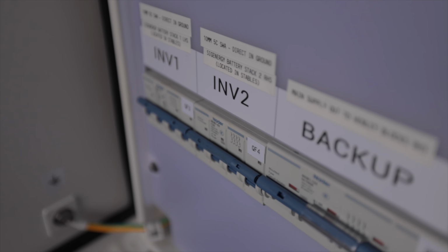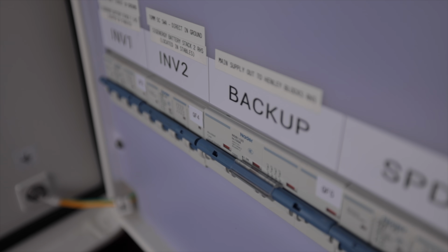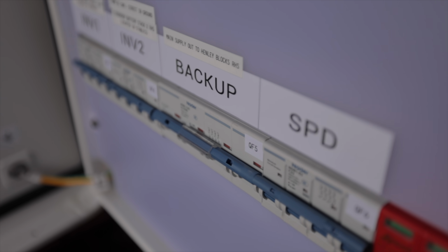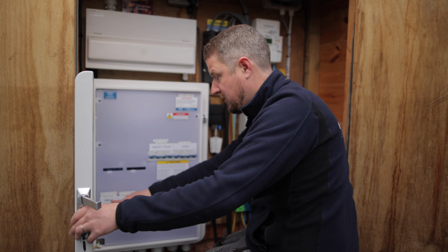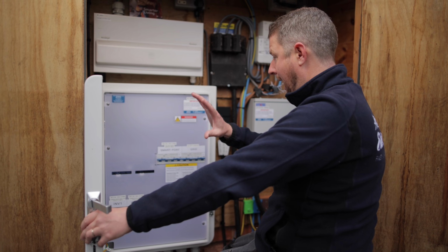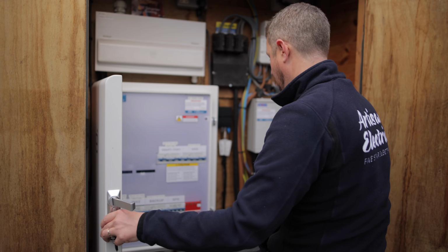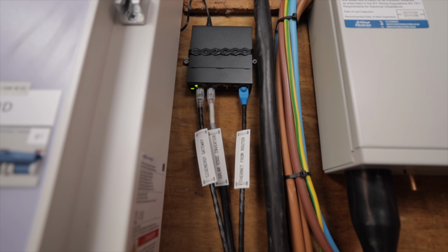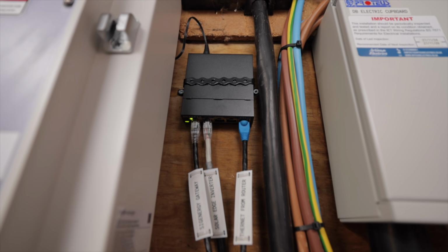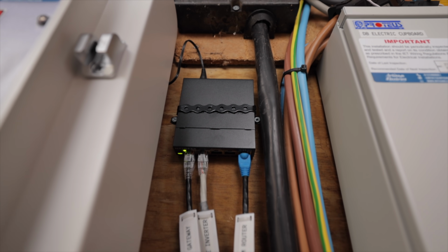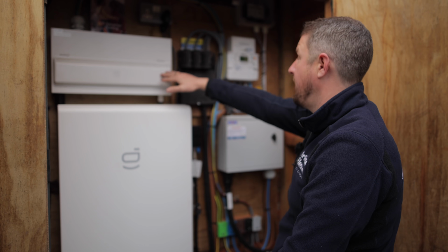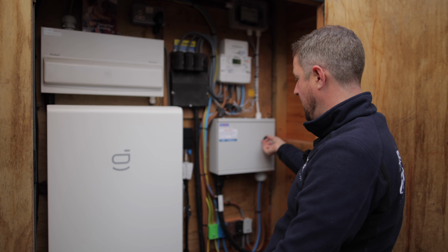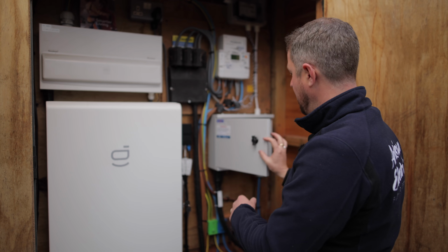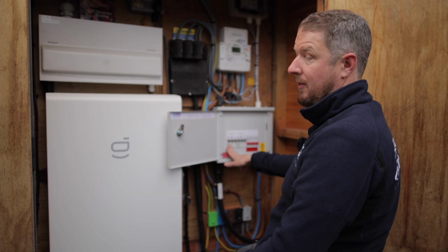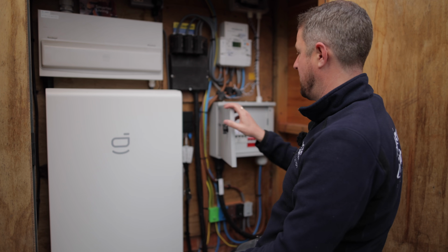The other side is the backup side, which feeds the house and all of the loads in the house. We've got a surge protection device here, and then our 2 battery inverters, and everything is neatly housed within this gateway. We've installed a network switch, which gives hardwired Ethernet connections to all of our devices. We've got the existing consumer unit here for the annex, as well as a new consumer unit that we fitted, and this feeds the main house.